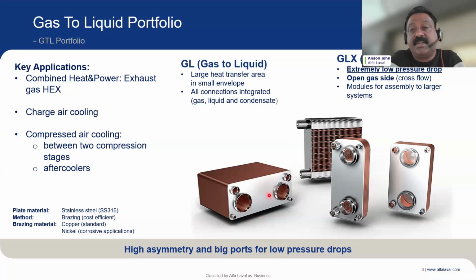These heat exchangers are not for big applications, but if you've got flue gas of 2,000 kg per hour or even up to 3,000 kg per hour, you can use this to do a lot of heat recovery. We had done a project in Australia in a food company, where they had flue gas coming in at 80 degrees C, and we were heating up the water from 15 degrees C to 65 degrees C using this small one.